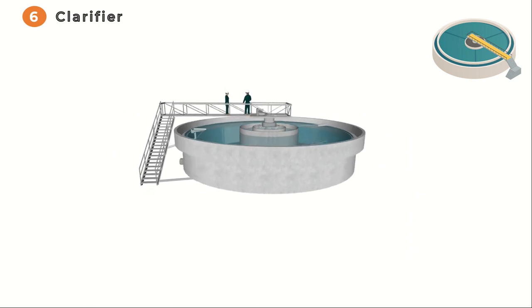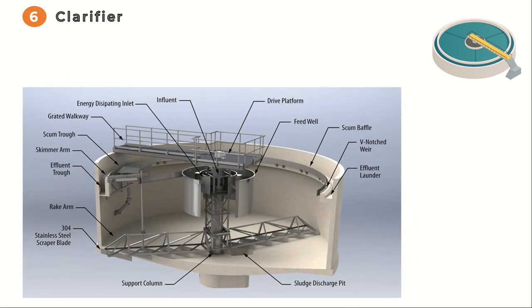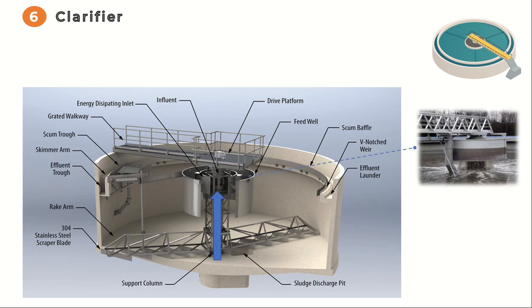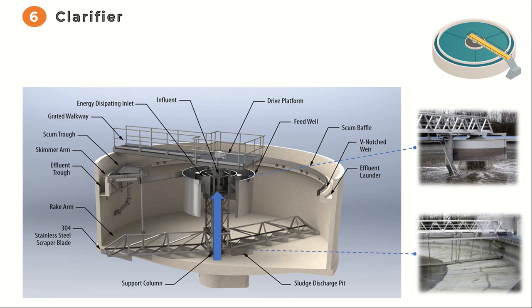The sixth step is final sedimentation. The secondary clarifier is an essential component of a wastewater treatment plant, playing a crucial role in the removal of suspended solids from the treated water before it is discharged. Comprising several key parts, the secondary clarifier ensures efficient solid-liquid separation. The wastewater enters the clarifier through the inlet, where it is distributed evenly across the settling zone. Within this zone, the velocity of the water decreases, allowing the suspended particles to settle down. The settled solids are then collected by a sludge collection mechanism, typically consisting of rotating arms or scrapers that slowly move across the bottom, gathering the accumulated sludge.